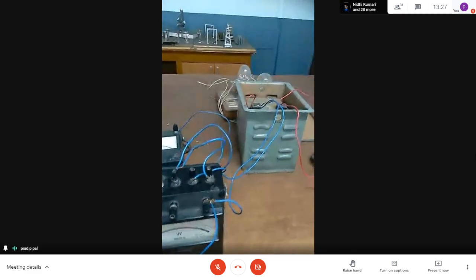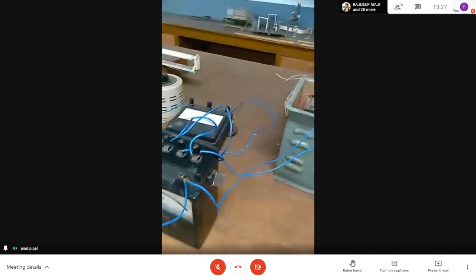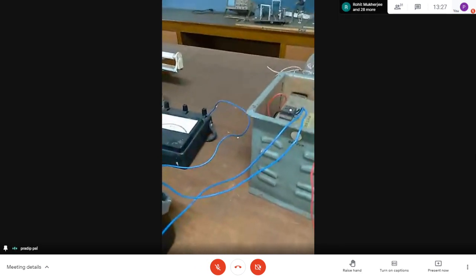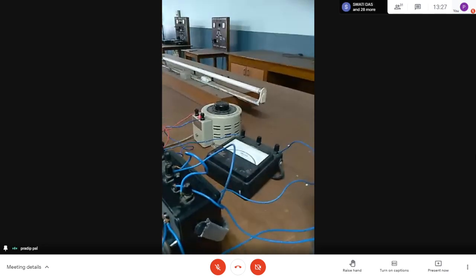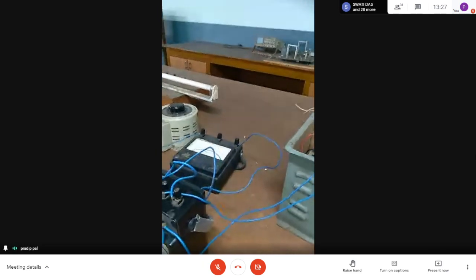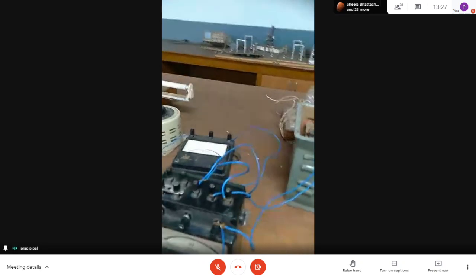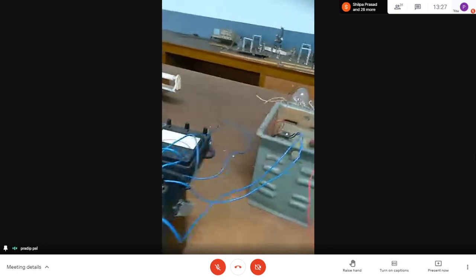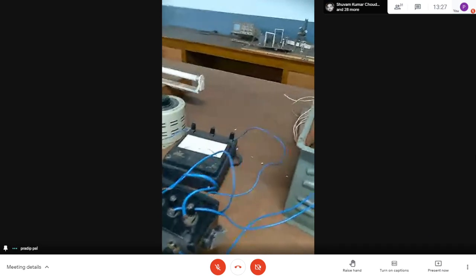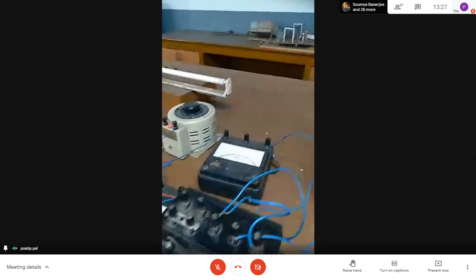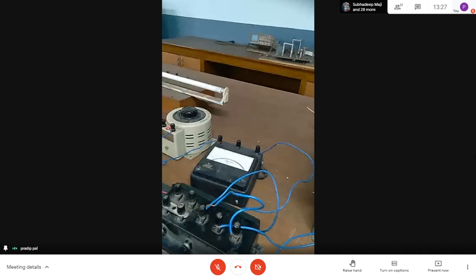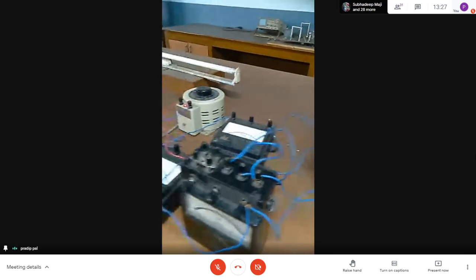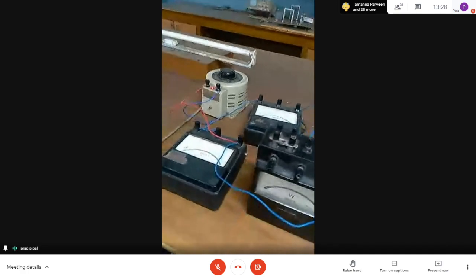What is the rated current for this transformer? We know P equals V times I times cos phi. For resistive load, cos phi is 1, so I equals P by V. This is a 1 KVA transformer, so P equals 1 KVA and V equals 230 volt. Therefore I equals 1000 VA divided by 230, which gives 4.33 ampere. So for this transformer the rated current is 4.33 ampere, and we will take only one reading at primary current 4.33 ampere.